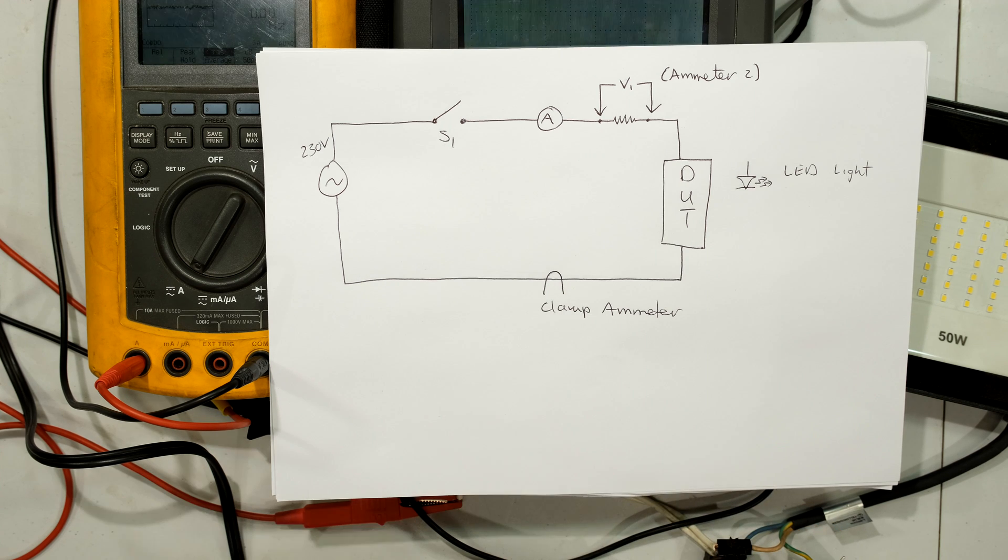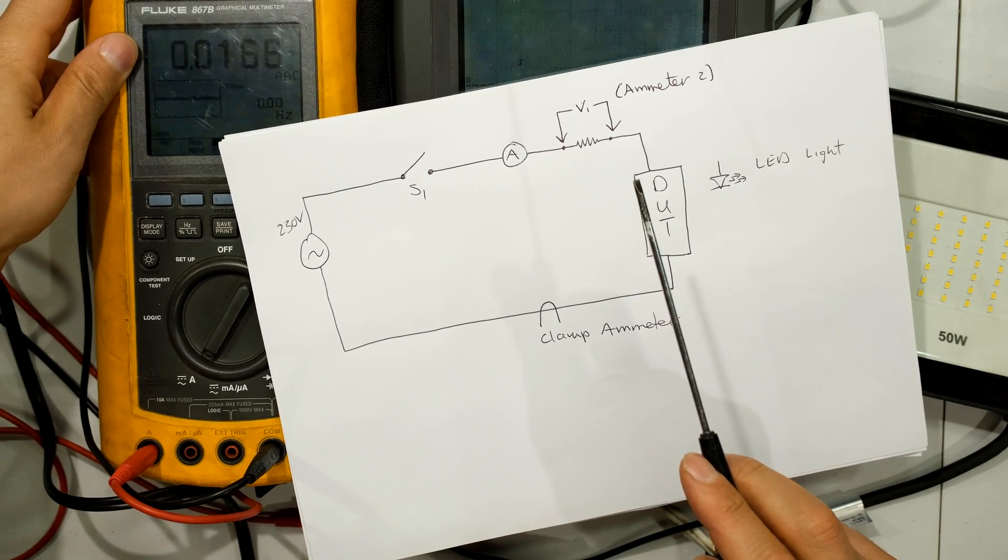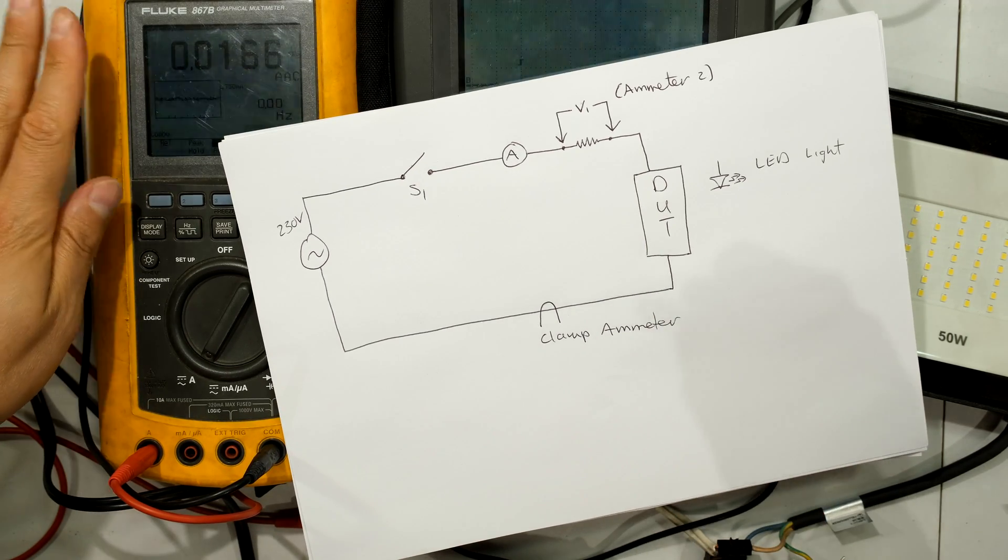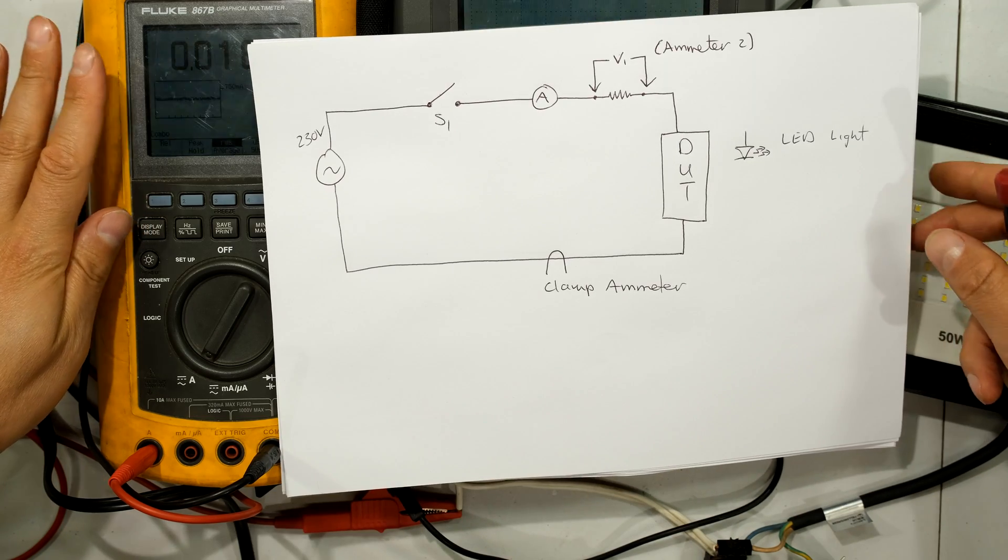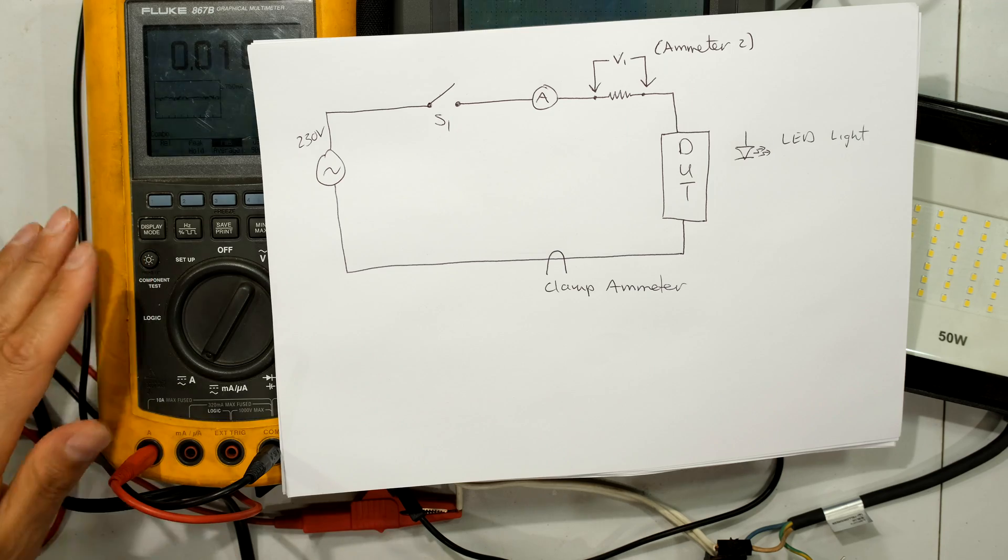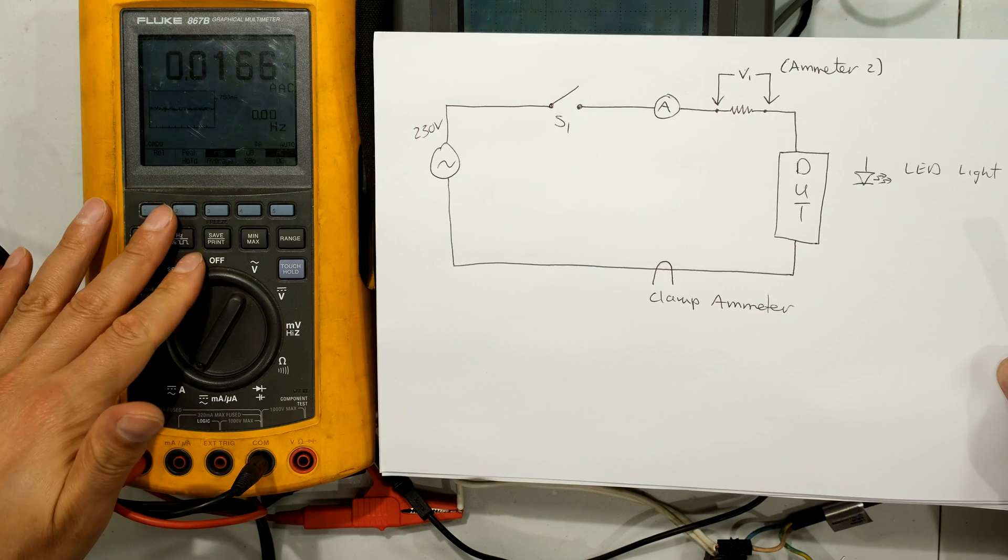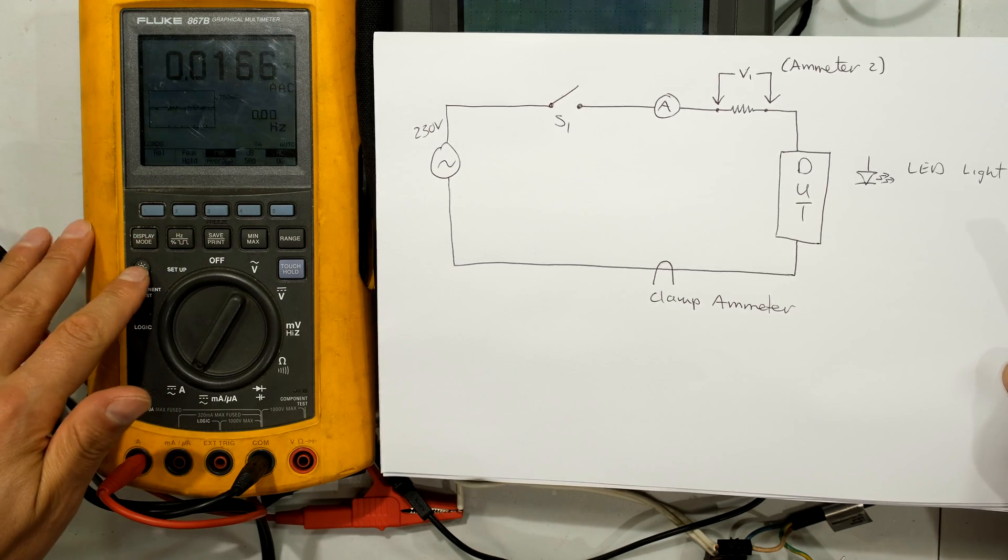In this circuit I actually have three current measurements. This ammeter here, the Fluke 867b meter, is extremely accurate but its response time is probably a bit too slow, so it's not picking up that minimum and maximum inrush current but it is extremely useful for the nominal current.